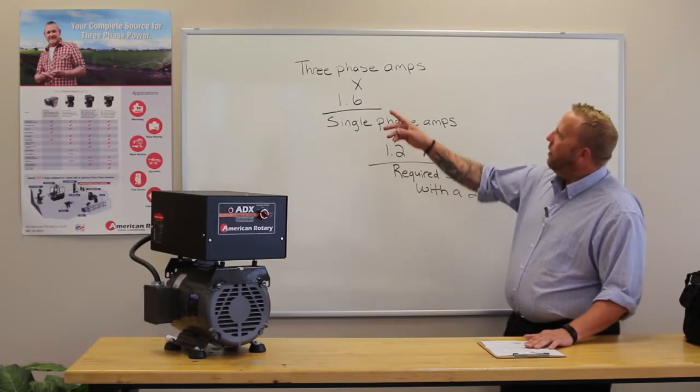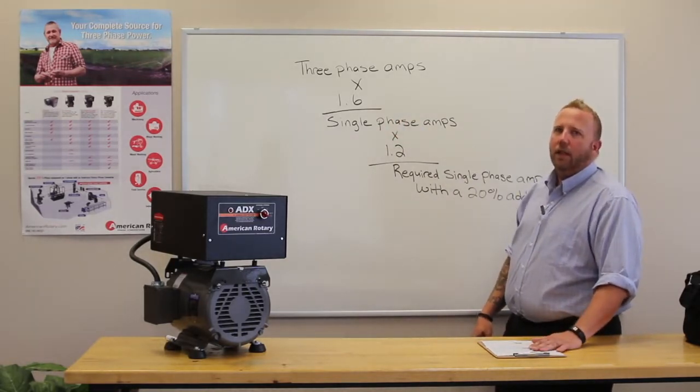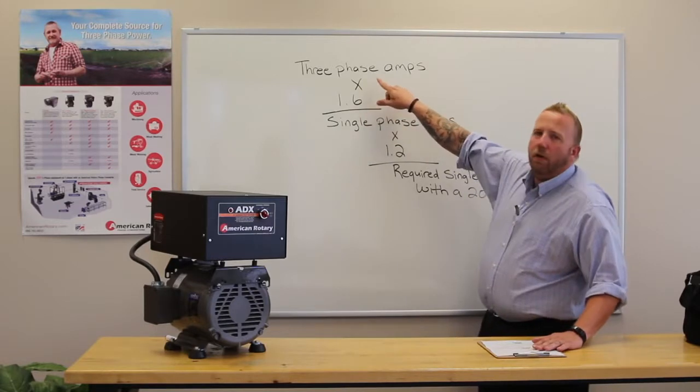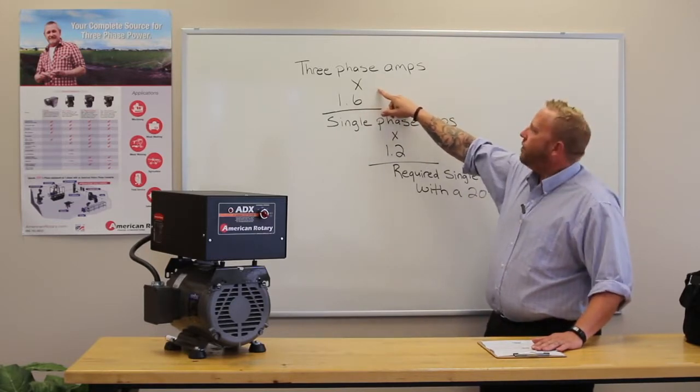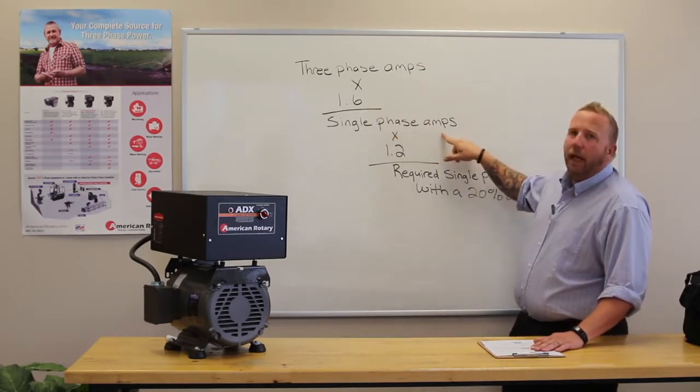So we have a formula here that tells you how to calculate what you're going to need on single phase. If you take your three phase amps of your load, multiply that by 1.6, you're going to get your single phase amps.